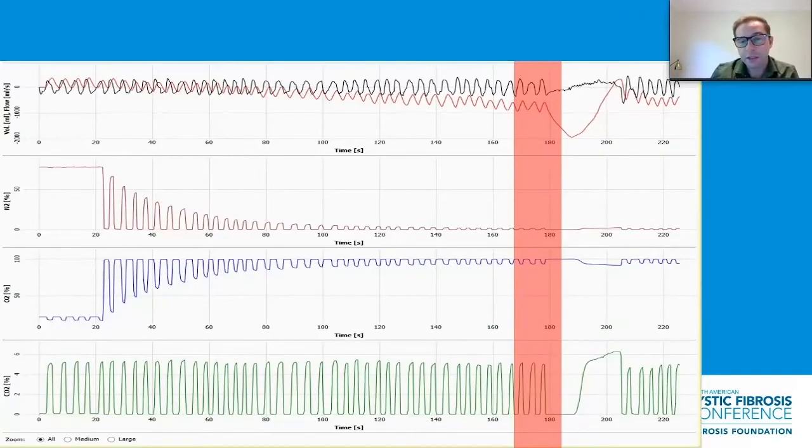This is what it looks like. So normally our target concentration would be reached at the start of that red shaded zone, and then we would stop the test around the end of that red shaded zone. But now we do a slow vital capacity, and our signal is the change in nitrogen concentration. So in this case, an increase in nitrogen concentration.